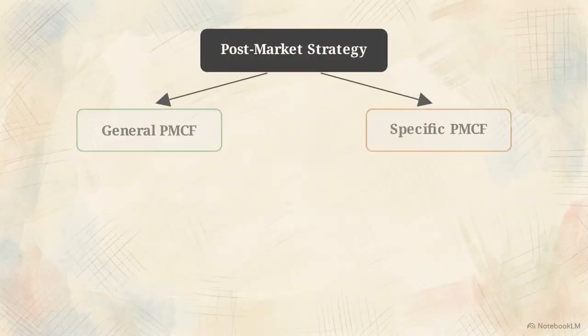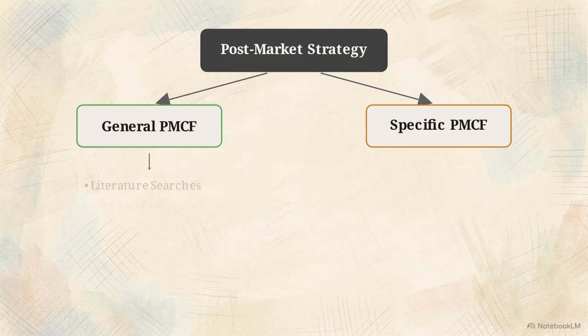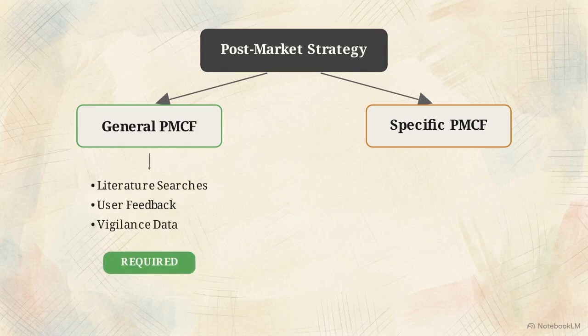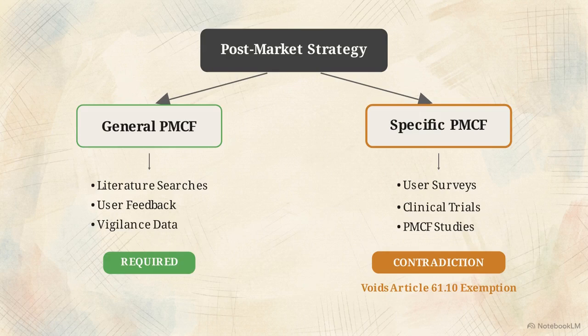There is also a significant regulatory consequence to providing mixed data. Including a small amount of low-quality clinical data, like old complaint logs or vigilance reports, can legally invalidate the non-clinical exemption pathway. This post-market workflow highlights a common contradiction in data collection strategies. Planning general post-market activities, like literature searches, is required. However, scheduling specific activities, like user surveys or trials, indicates that human data is actually necessary to confirm safety. Even a flawlessly tested device will be rejected if the technical documentation accidentally implies a future need for human clinical data.